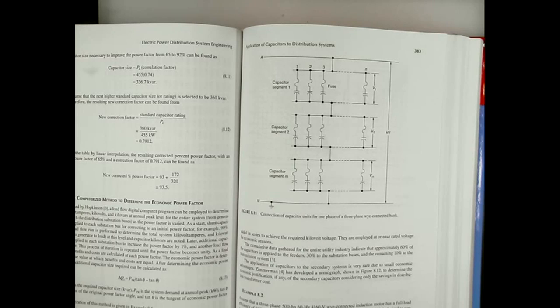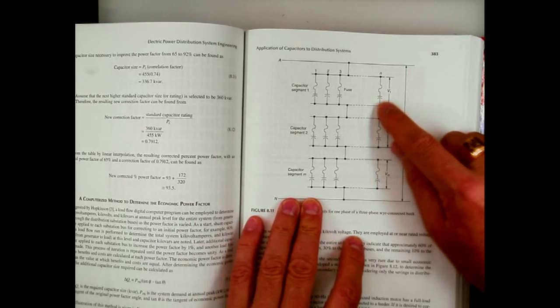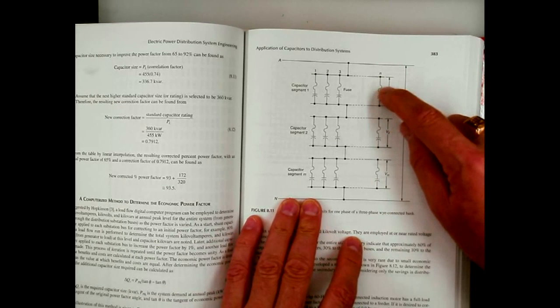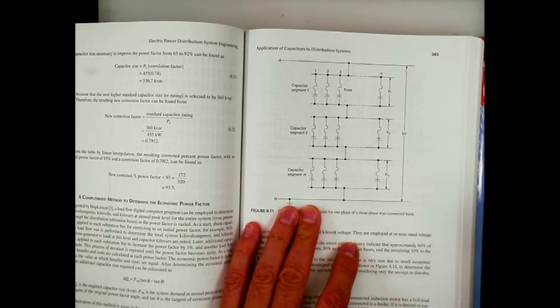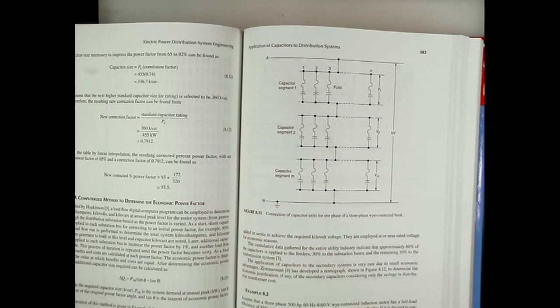It's called reliability, right? You have to avoid that a failure in one of those capacitors brings down the entire bank. So what happens is, if something goes wrong here, that fuse will blow. What happens? It opens, and what happens? You isolate it.